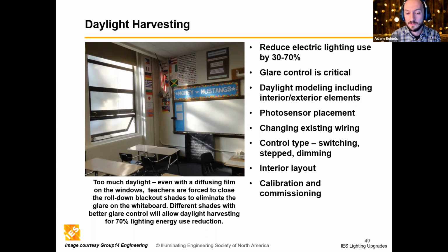In a retrofit, this includes modeling properly, placing photosensors exactly where they go in the room for the right pickup, rewiring, and new controls. After all this, you have to make sure the light you let in isn't glare. Basically you need blinds that aren't blackout shades—more just to reduce the illumination, not completely cut it off.